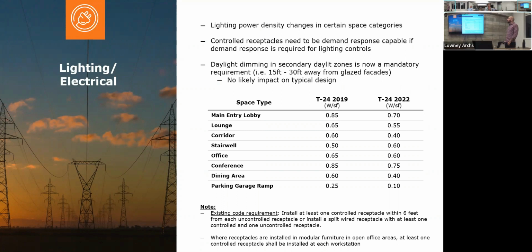In terms of daylight dimming, no major changes except the code requires your spaces to be split into 2 daylighting zones when you have a window like this one. Your first daylight zone would be 15 feet away from the wall or a distance equal to your wall height. And then the second row would be the same length, next to that first primary zone. So previously you only were required to provide daylight dimming controls for the primary daylight zone. Now you have to do both primary and secondary daylight zones.